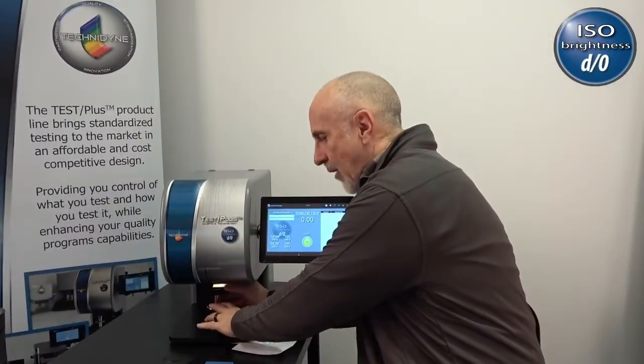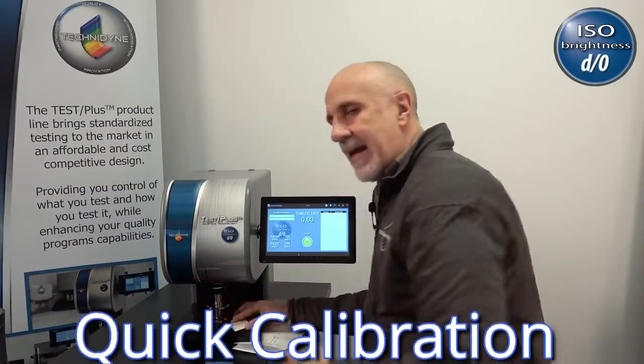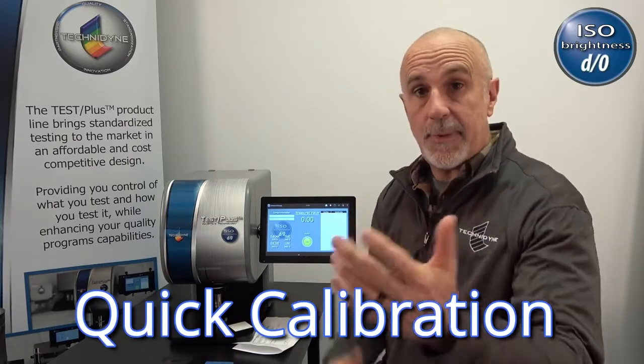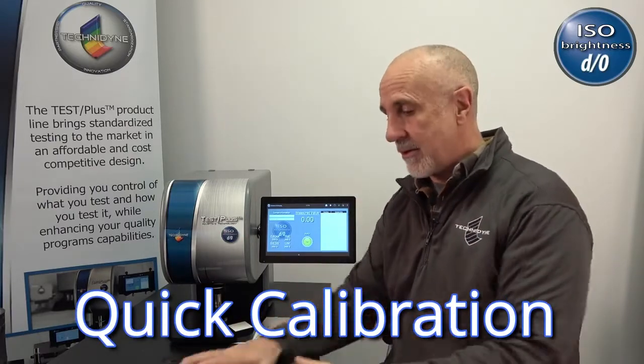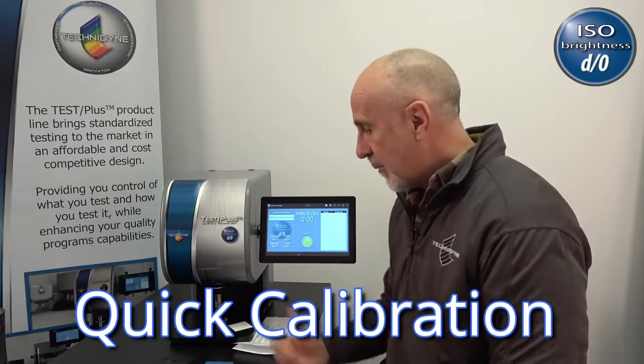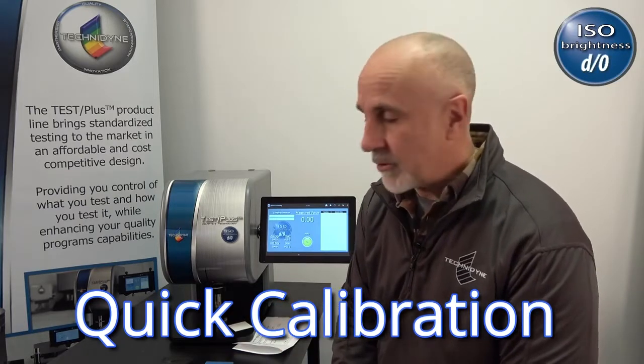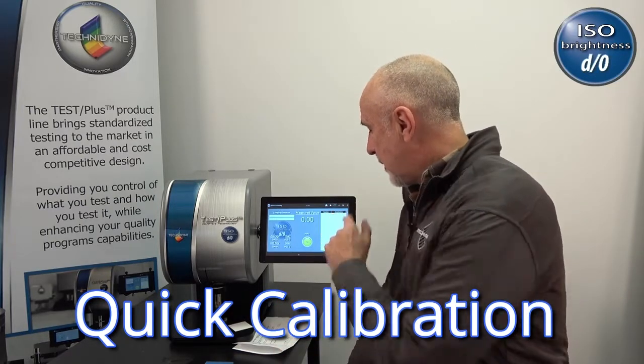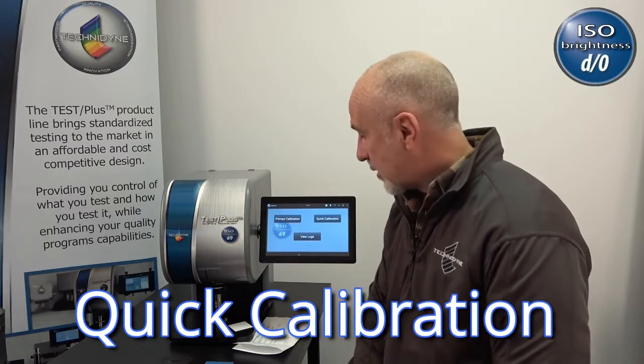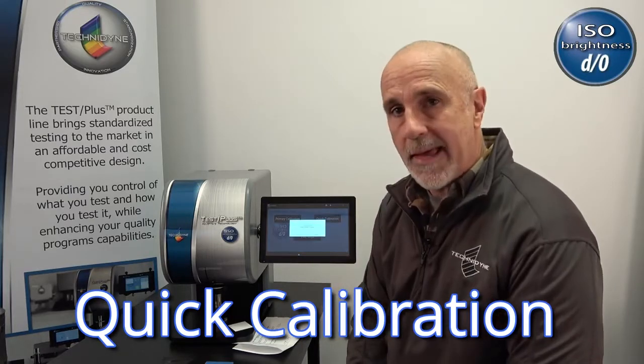Now, if I want to do the quick calibration, and this is what you'll probably do on a shift-by-shift basis or a daily basis, you don't have to use the paper standards, but you're going to use the working standard to do that. So in that case you go back to the calibration screen, and this time you'll choose quick calibration.